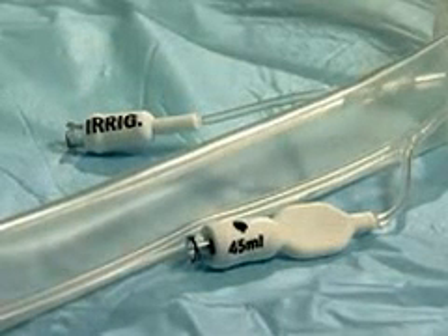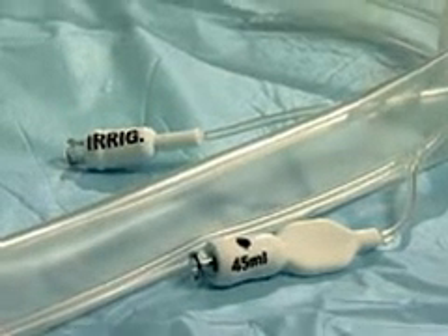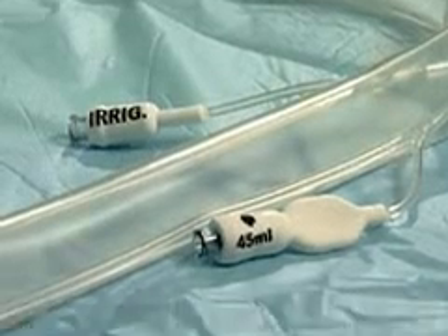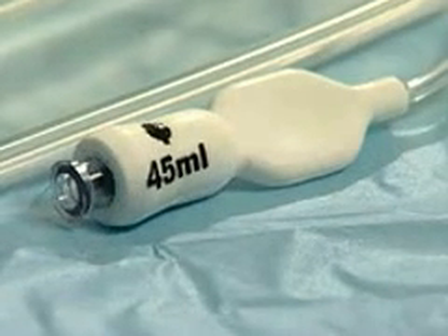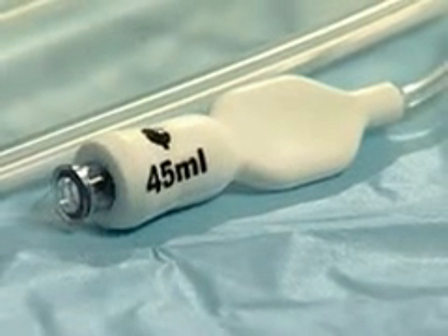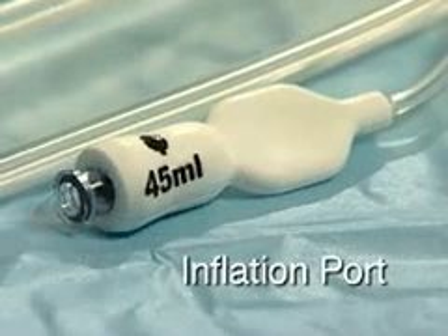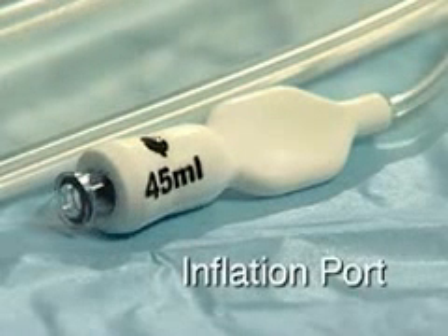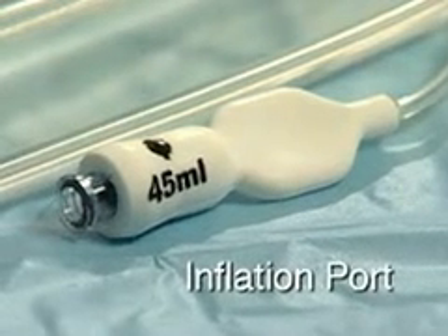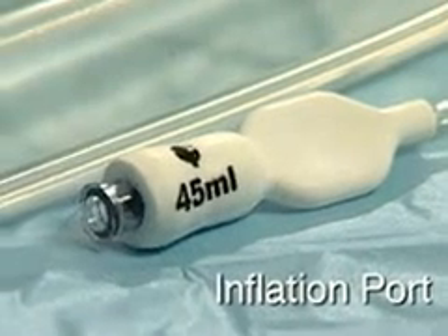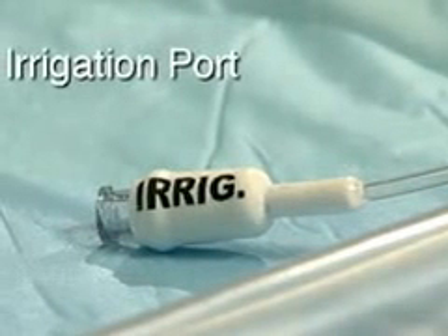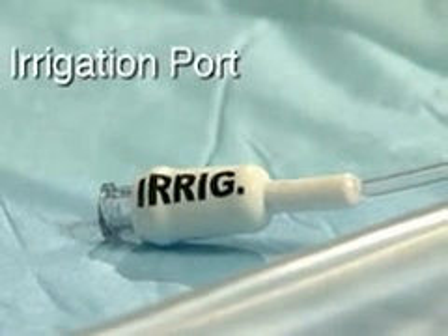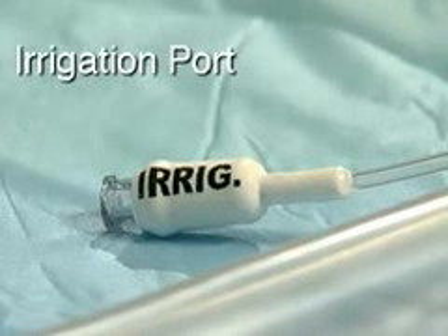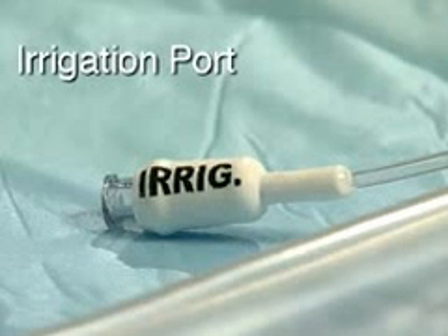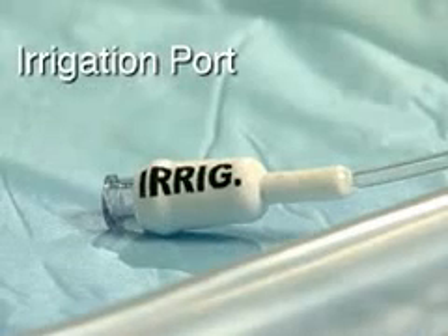Two small tubes, each with a port, are attached to the silicone catheter. One port with 45 ml printed on it is used to inflate the retention balloon after the device has been inserted into the patient's rectum. It is called the inflation port. Another port with IRRIG printed on it is used to flush the catheter if it becomes blocked with solid particles. It is called the irrigation port.